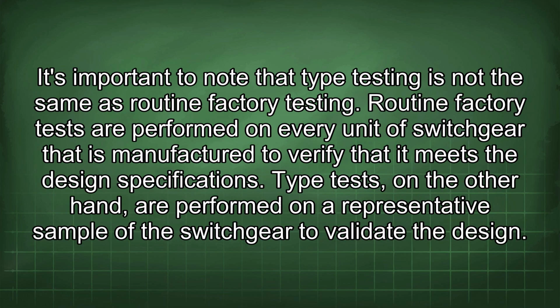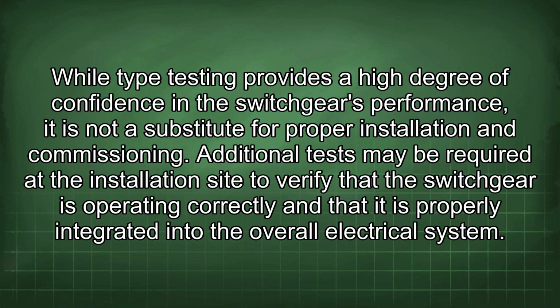It's important to note that type testing is not the same as routine factory testing. Routine factory tests are performed on every unit of switchgear that is manufactured to verify that it meets the design specifications. Type tests, on the other hand, are performed on a representative sample of the switchgear to validate the design. While type testing provides a high degree of confidence in the switchgear's performance, it is not a substitute for proper installation and commissioning. Additional tests may be required at the installation site to verify that the switchgear is operating correctly and that it is properly integrated into the overall electrical system.